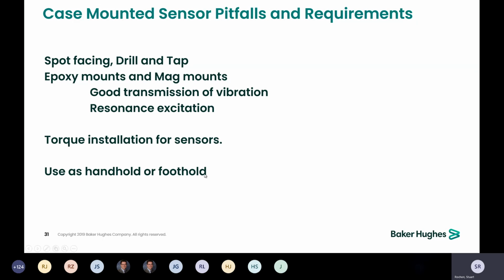You also want to either label them or protect them so that people don't use them as handholds or footholds to climb up on the machine. Again, that torque issue where you can crack the crystals or damage the sensor or get it out of orientation with the machine because they bend it.